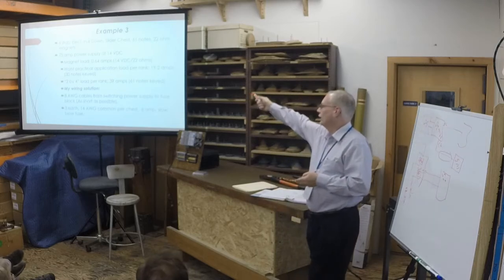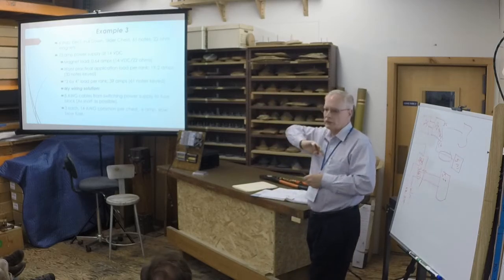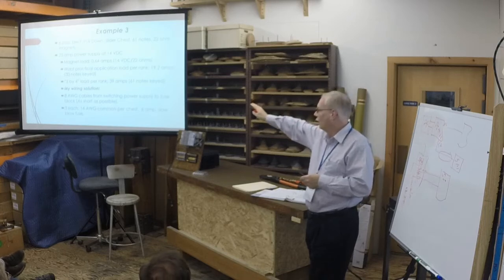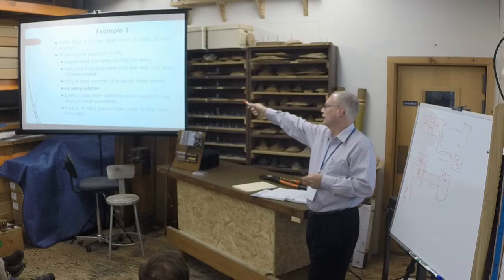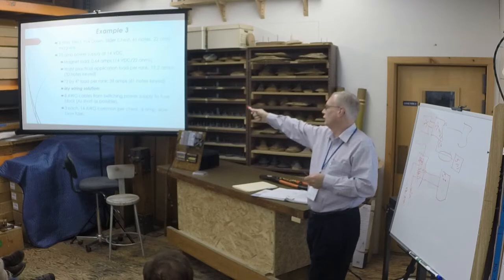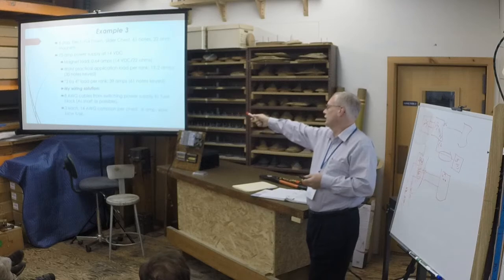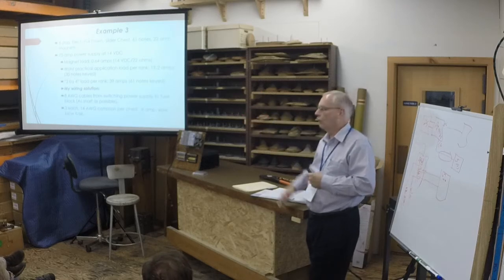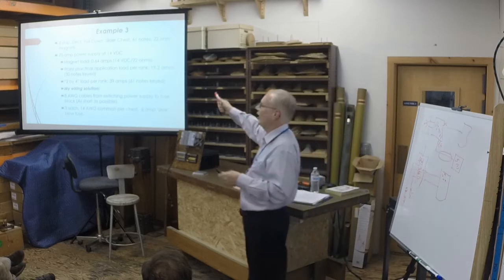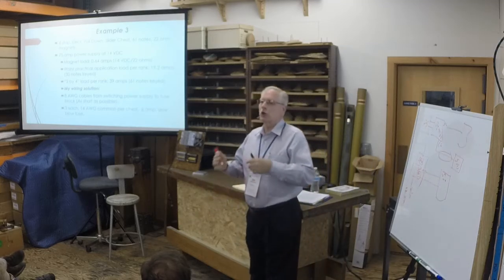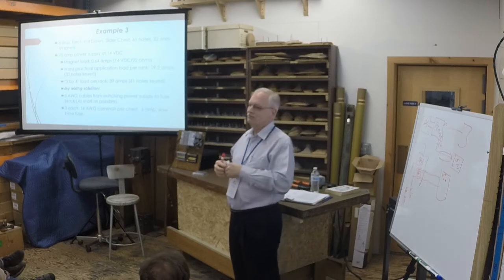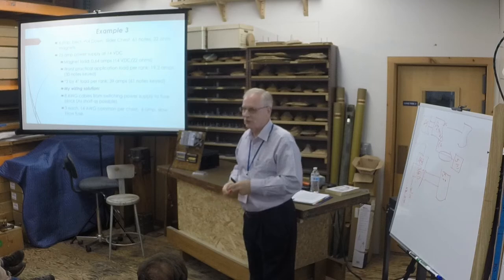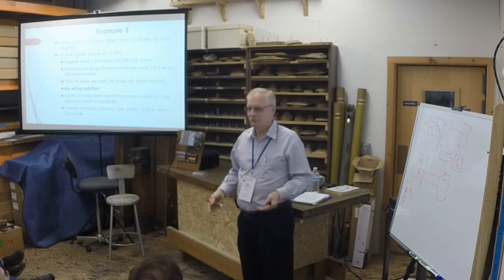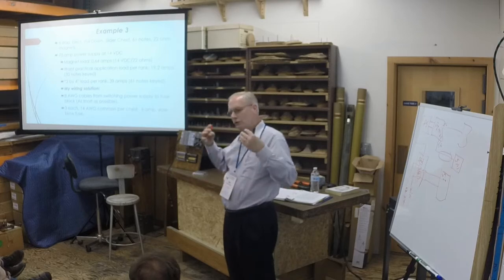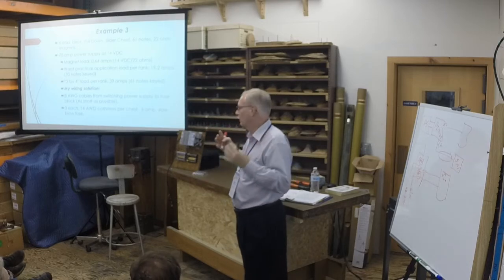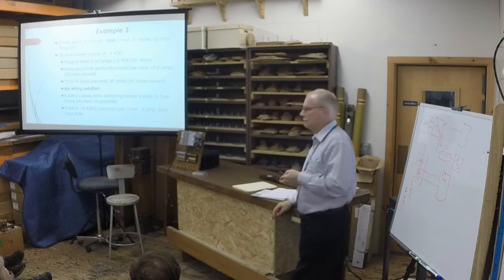19.2 amps, I have not taken into consideration slider motors or whatever. Your worst case is 39 amps. Again, 8 AWG from power supply, 3 14 gauge per chest, 6 amp slow blow per feed, which gets you 18 amps. On a slow blow, it gets you probably 20% more forgiveness, okay, rather than throwing another fuse in. Because again, I'm going back to what's the real world gonna be?